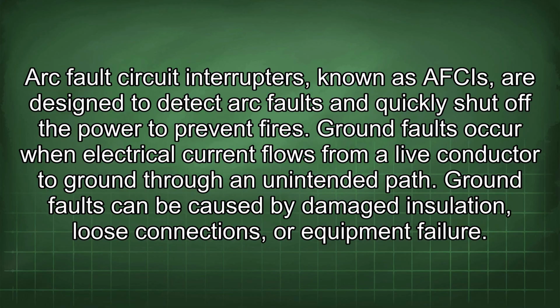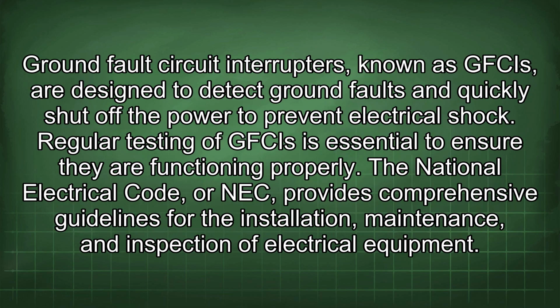prevent fires. Ground faults occur when electrical current flows from a live conductor to ground through an unintended path. Ground faults can be caused by damaged insulation, loose connections, or equipment failure. Ground fault circuit interrupters, known as GFCIs, are designed to detect ground faults and quickly shut off the power to prevent electrical shock. Regular testing of GFCIs is essential to ensure they are functioning properly.